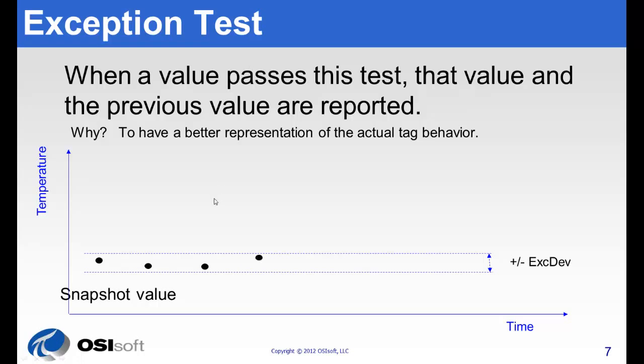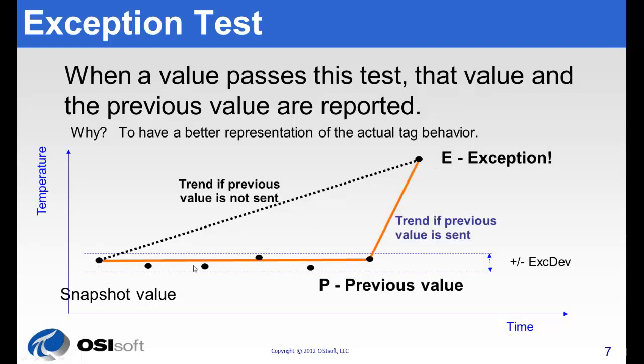As we go on, raw values are falling within our dead band. We see one has fallen out, so this is an exception, and we're going to keep it. However, if we just stored the snapshot value and the new exception value, we'd miss what was actually going on with the data. So we end up sending the previous value as well, the exception and the one right before it.